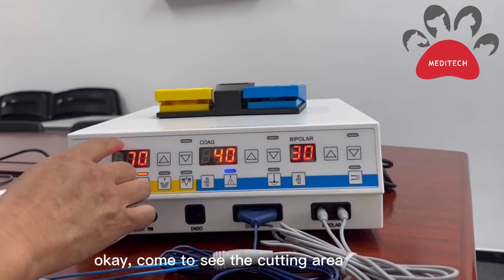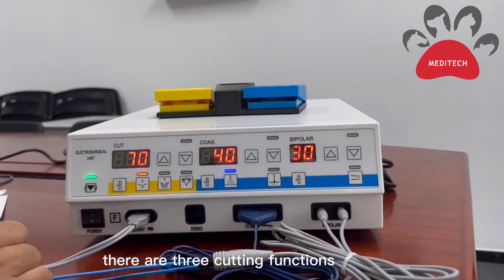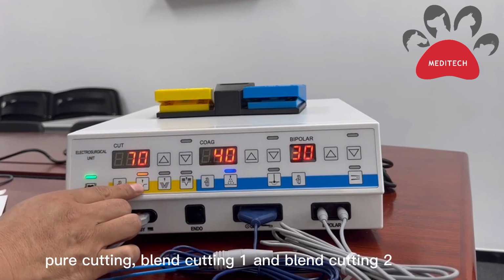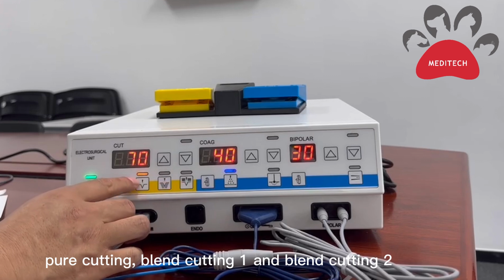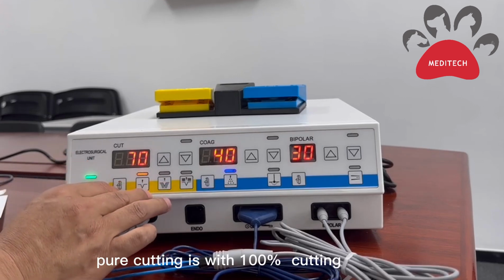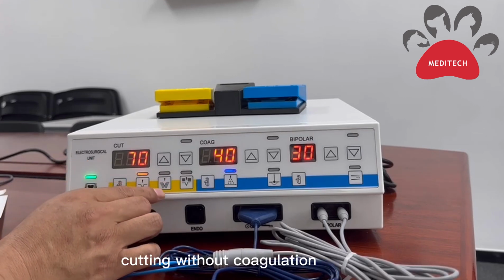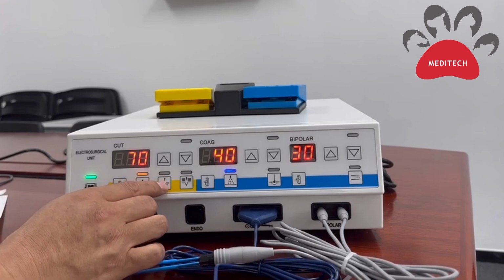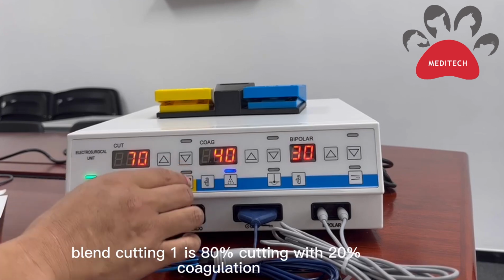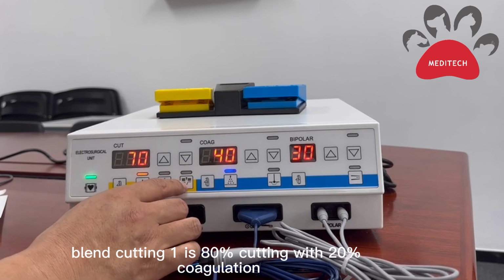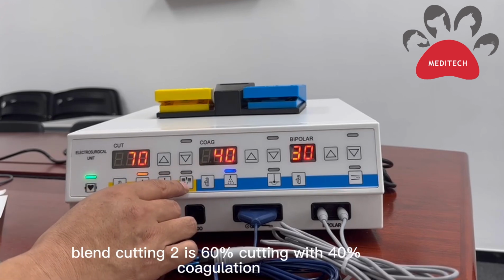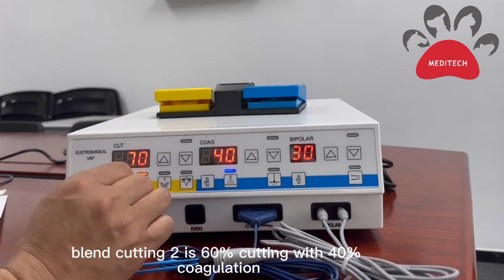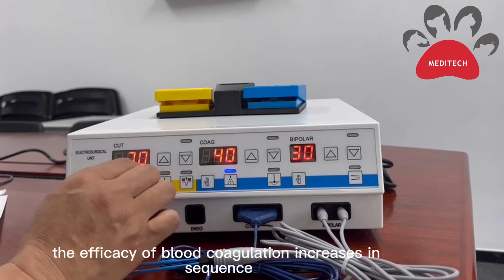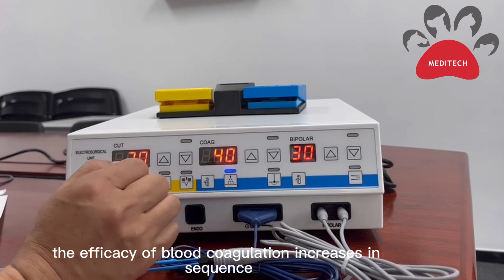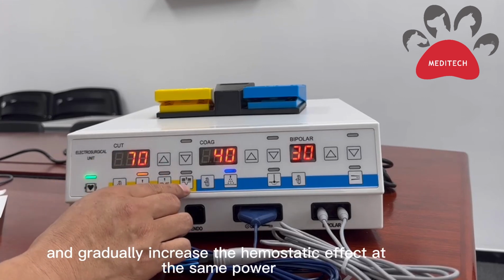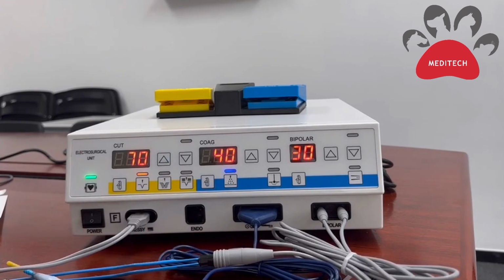Okay, come to see the cutting area. There are 3 cutting functions: pure cutting, blend cutting 1, and blend cutting 2. Pure cutting is cutting at 100%, cutting without coagulation. Blend cutting 1 is 80% cutting with 20% coagulation. Blend cutting 2 is 60% cutting with 40% coagulation. The efficacy of blood coagulation increases in sequence, gradually increasing the hemostatic effect at the same power.